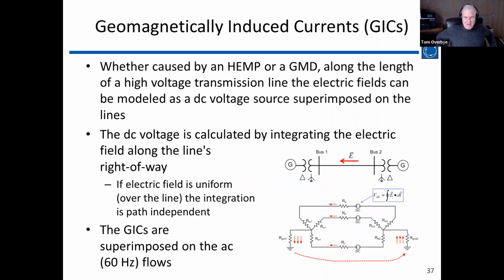When we have a time varying electric field superimposed on the transmission grid, because it's changing relatively slowly, we call it quasi-DC. It varies with time, but at much less than a hertz, so from an AC perspective it looks like DC. The electric grid just looks like a big DC circuit. The grid itself is 3-phase, but from a DC perspective all the conductors look parallel. So to model electric field variations along a transmission line, we integrate the electric field along the length of the line, and it looks like a DC current and DC voltage. We take that Thevenin equivalent and convert it into a Norton equivalent, which lets us solve the electric grid as though it were a DC circuit.